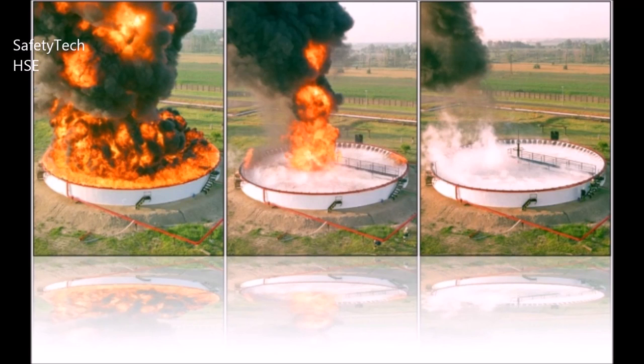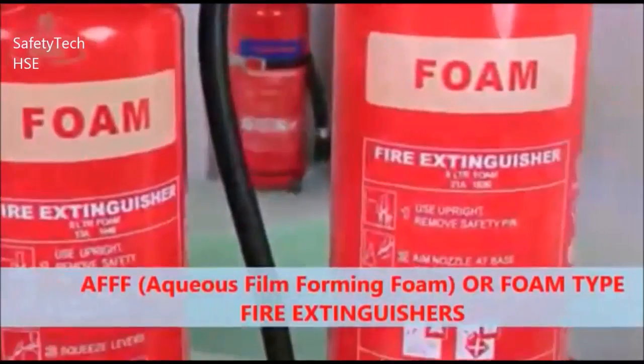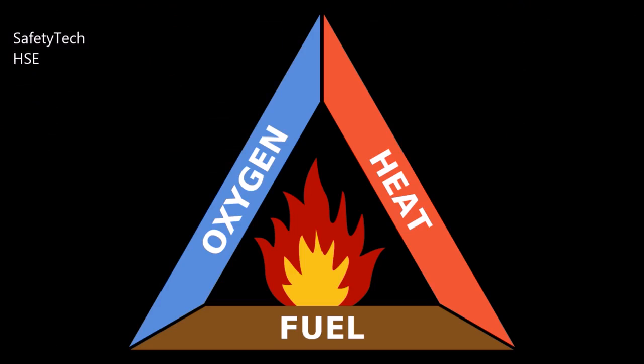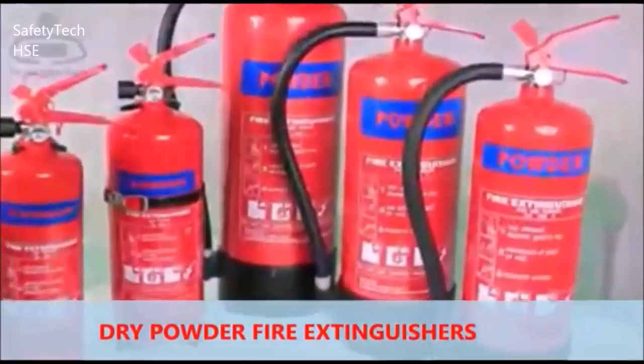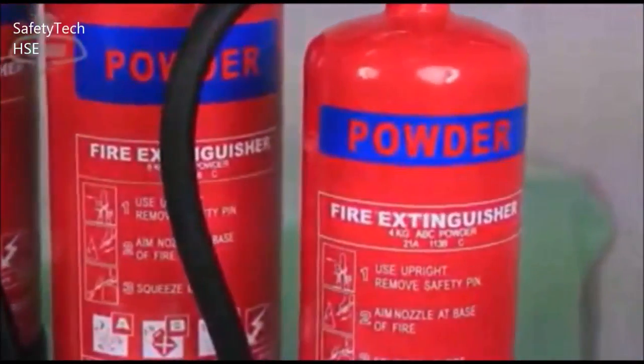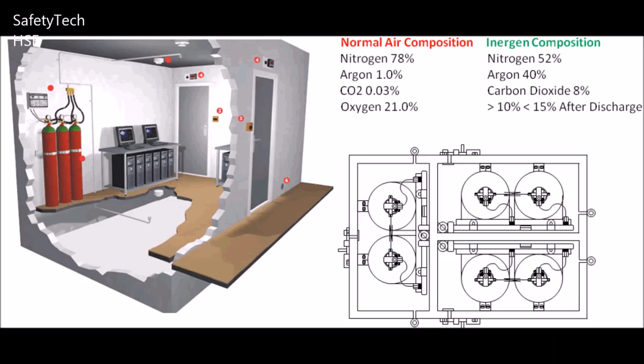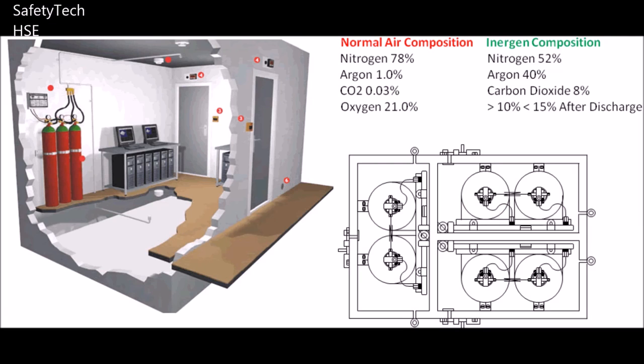Foam also tends to prevent the formation of flammable vapor. Another method of smothering is by the application of a cloud of finely divided particles of dry powder, usually sodium bicarbonate, from a pressurized extinguisher. Another class of smothering agent may be described as temporary in its blanketing effect — the vigorous discharge of an inert gas such as carbon dioxide or nitrogen in the immediate vicinity of the fire may reduce the oxygen content sufficiently that combustion cannot be maintained.